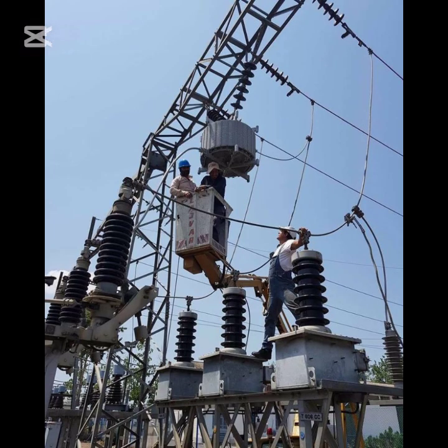This is why wave traps or line traps are installed in series with the transmission line. These line traps obstruct high-frequency signals, allowing only the 50 Hz frequency signals to pass through to the switchyard equipment. Additionally, they provide protection against surge voltages.